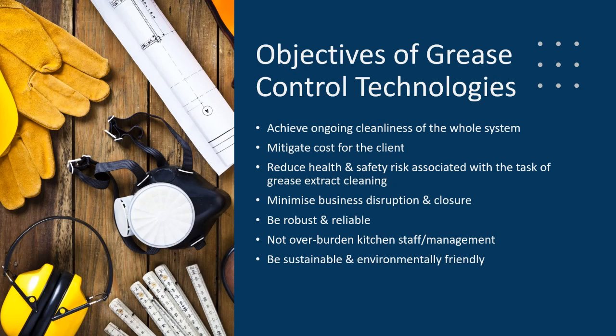When innovators looked at the challenges of grease control, they considered various objectives and are generally trying to achieve the following. Firstly, ongoing cleanliness. The grease starts to build up immediately after a grease extract clean, and it continues to build until the next clean. Is that 3 months? 6 months? 1 year later? We see huge micro levels of grease in systems after relatively short periods of time. I could show you photos, but it's lunchtime.